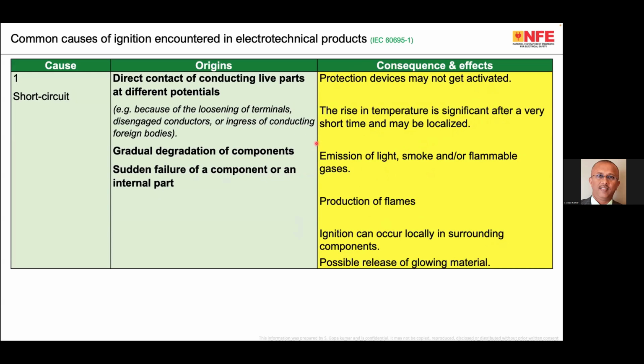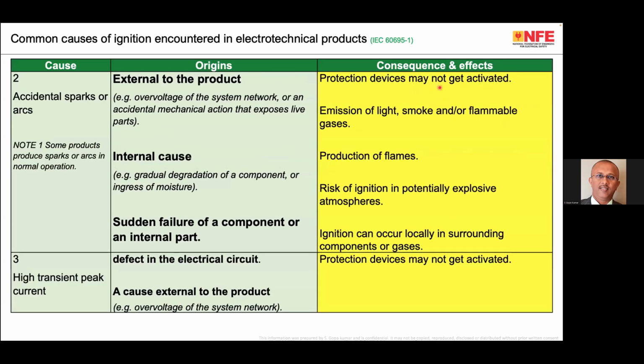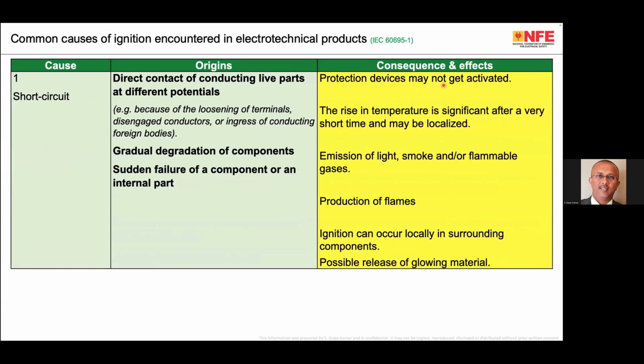But if we analyze the entire installation after a fire incident, most often the reason is serial number one, protection devices may not get activated, or the rise in temperature is significant after a very short time and may be localized. These two are the majority of the reasons for fire from short circuit. If the protective device is working properly, then there is no chance of fire. There is a short circuit, but the device tripped as a result. No fire. That is the way it should be.